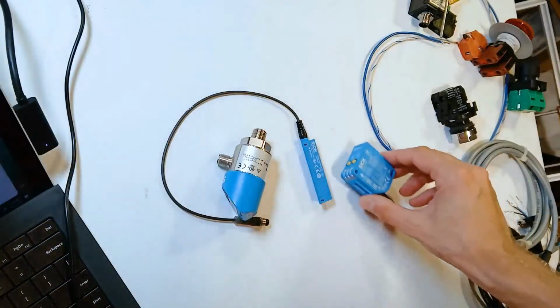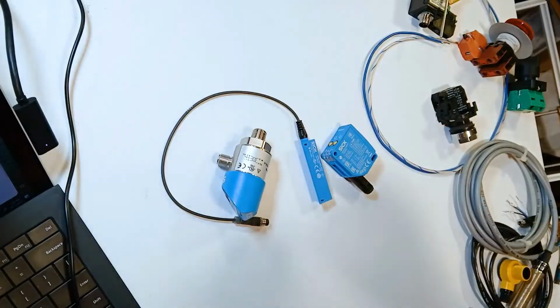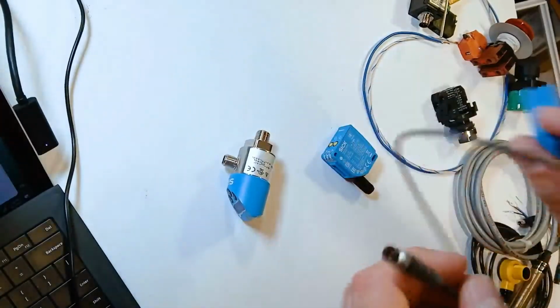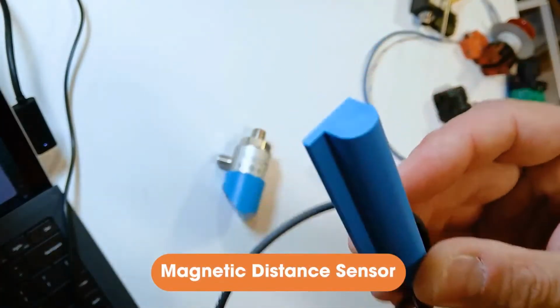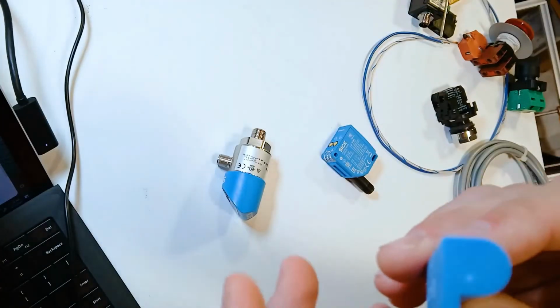That is one of the nice things about I/O link sensors, is very often they will also have the capability to act as discrete sensors, so you can use them as replacements into your system even if you don't yet have I/O link. Here is a distance sensor that's a magnetic distance sensor that's designed for attaching to the side of a pneumatic cylinder.